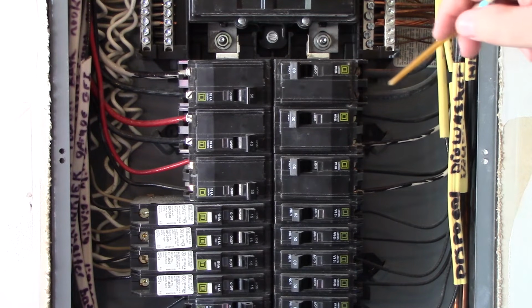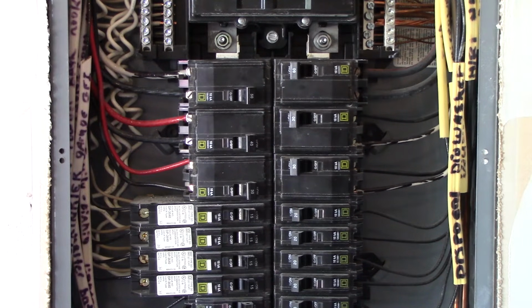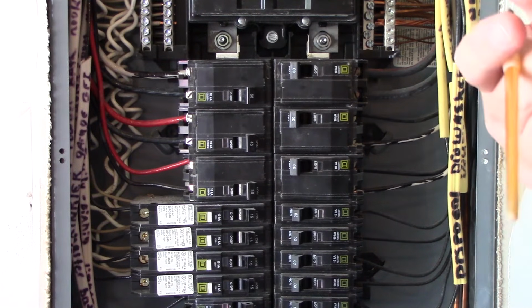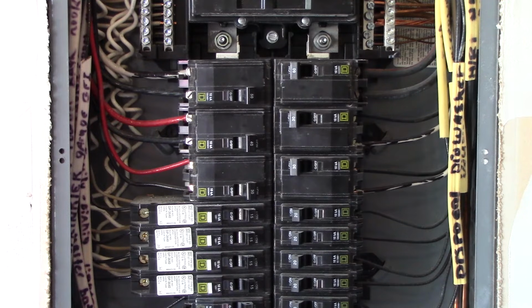Okay, and so this happens to be a copper conductor here, and this happens to be a 6 gauge copper, and it's on a 60 amp. Again, in that application, it is based on the nameplate rating that says the maximum overcurrent protection, minimum circuit size.